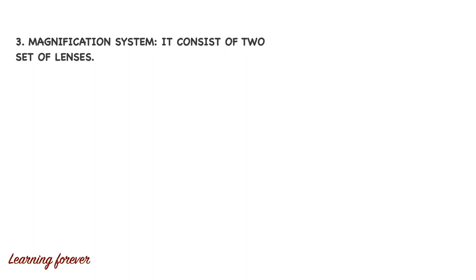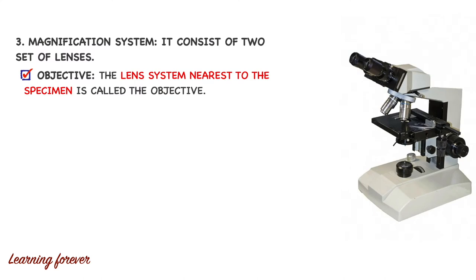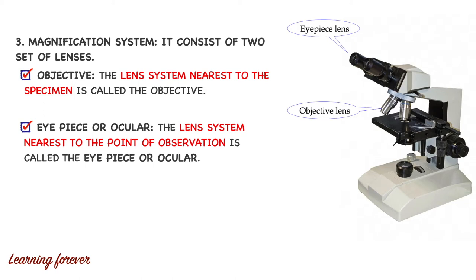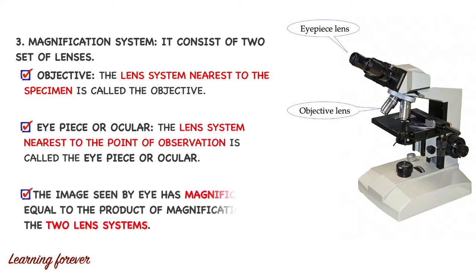Third is the magnification system, which consists of two sets of lenses. The first is the objective lens — the lens system near to the specimen is called the objective lens. The second is the eyepiece or ocular — the lens system near to the point of observation. Since we are using two lenses, the total magnification seen by the eye equals the product of the magnifications of both lens systems. For example, if the eyepiece lens is 10x and the objective lens is 40x, total magnification will be 10 × 40 = 400x.